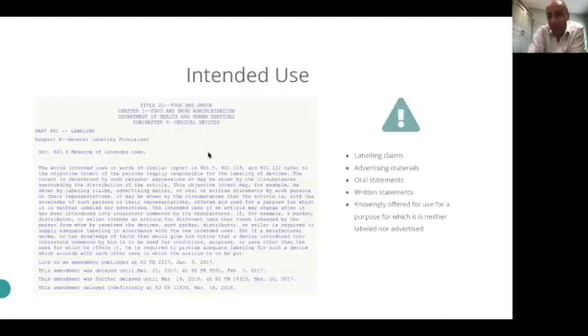How do you figure out what risk class you are? Well, you need something called an intended use statement, and you'll need this whether you're applying in America or Europe. And here's how the FDA define the intended use. You should consider an intended use really as what you want your product to do on the packaging and labeling that comes with it. So how do you describe your device? And something really important to know about intended use is that words matter. The words you use to describe your device, the claims you want to make, really matter. And if there's any piece of your regulatory documentation that the regulators will spend a lot of time on, it is the intended use statement. And it's really a very useful tool.